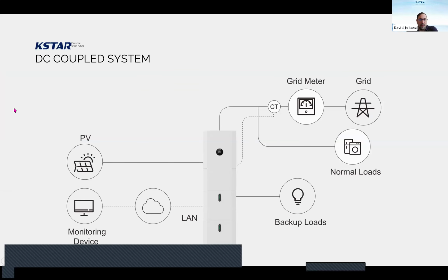Let's check a DC coupled system. It means that we can attach PV to our system by DC, and we can discharge it and deliver the energy to the AC. It also has a separate backup load, and the monitoring can go through the LAN or by Wi-Fi in case of a logger stick. And the meter needs to be connected to the nearest connection point of the grid. There is an arrow inside, and the arrow needs to point to the grid.